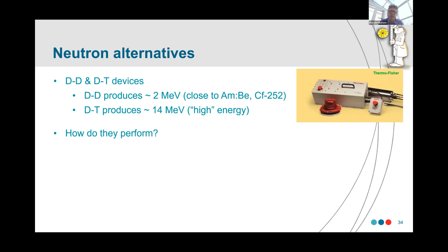And then DT produces something around 14 MeV, what we call high energy, although it isn't as high as we would like for all our applications. How do they perform? Always important, and this is information from my colleague Jean-Paul Archambault on characterizing our DT device, and this is changing the beam current and looking at the count rate, and as you see that it is a non-linear response. The repeatability is also at the few percent level.